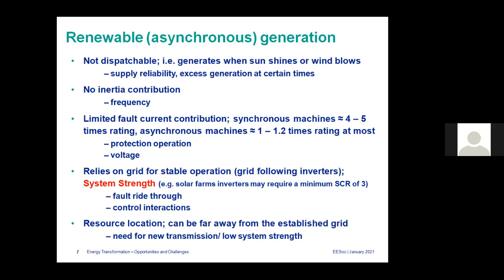It's the same with fault current contribution. Normally with synchronous machines, we know we have about 4 or 5 times the rating. If a 100 MVA synchronous machine has a fault, you can expect about 500 MVA fault current or fault level contribution. But asynchronous machines, or solar farms and wind farms, you hardly see more than their rating as the fault current contribution. So the problem is if you don't have enough fault current when there is a fault, sometimes you struggle to detect the faults, especially if you are relying on overcurrent protection, especially in distribution systems or low voltage systems. But there are solutions for those as well. Sometimes you can look at differential protection and the like. So there are solutions, but sometimes they are expensive.